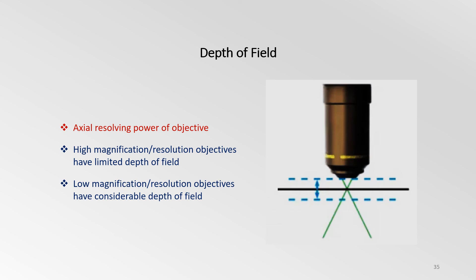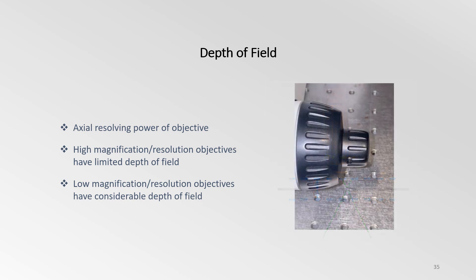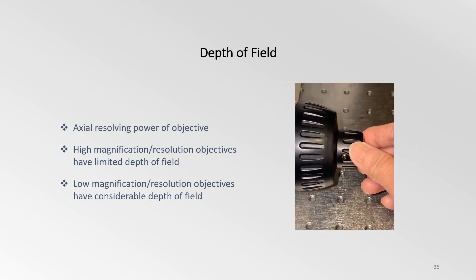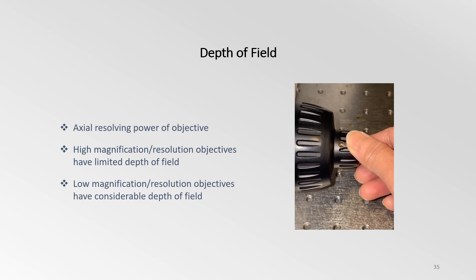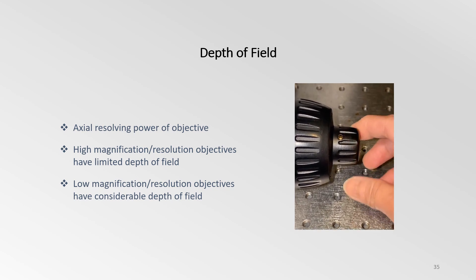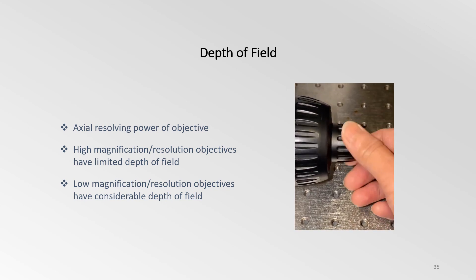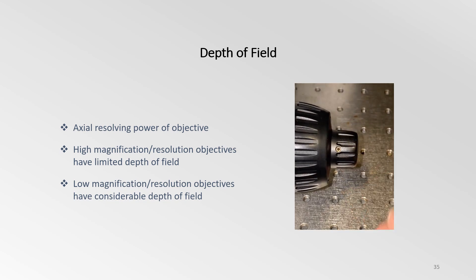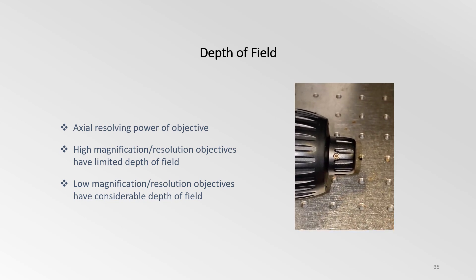A higher NA will give a higher resolution, but the depth of field becomes considerably smaller. Low-resolution objectives have larger depths of field. This is exactly the reason why the fine focus adjustment on the microscope must be set delicately and precisely for objectives with high NA. Whereas for low NA, a few turns of the focus knob may seem to make no difference to the image.